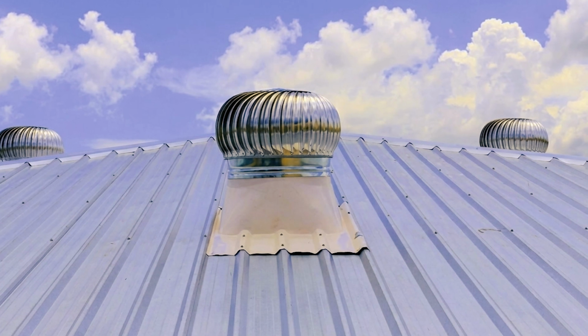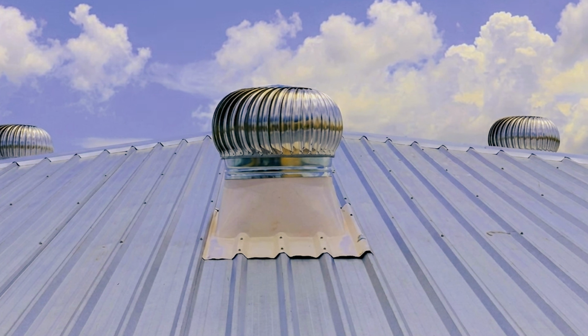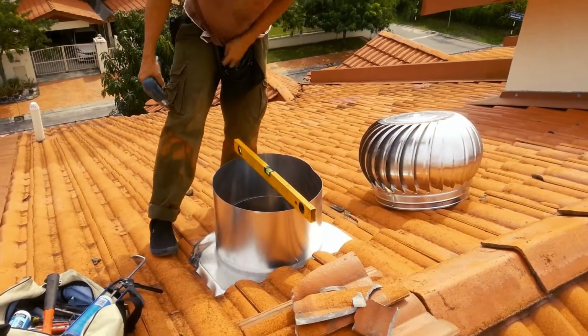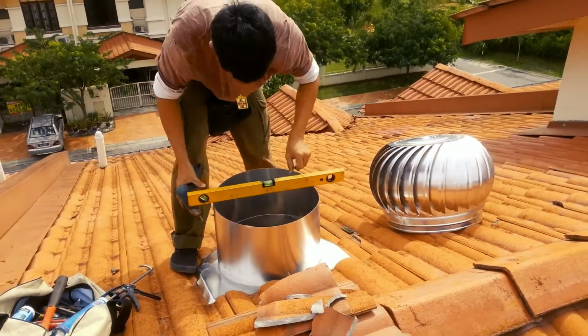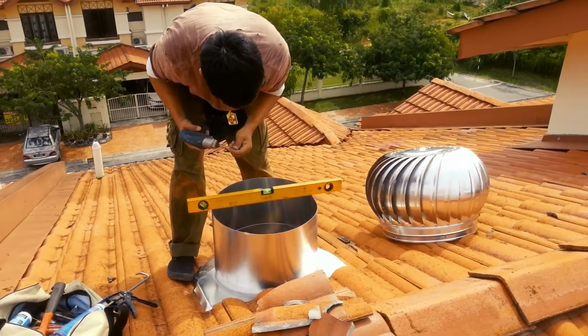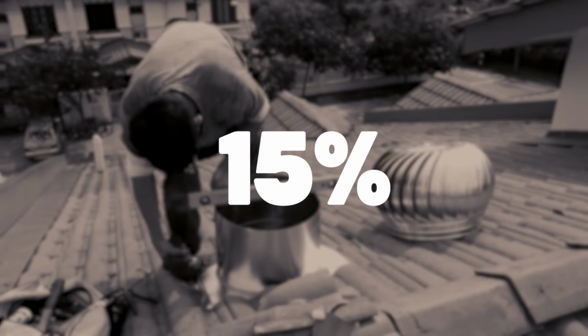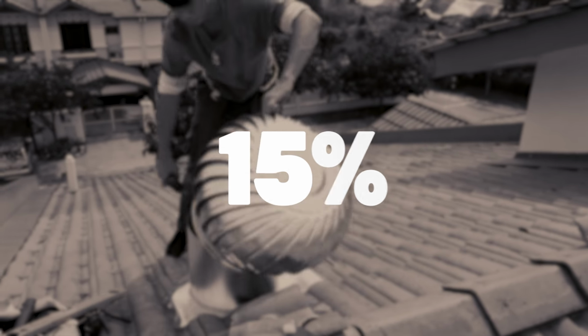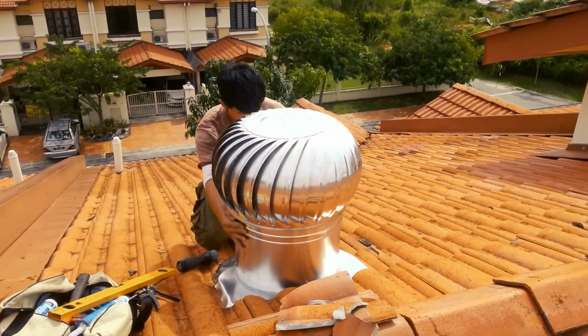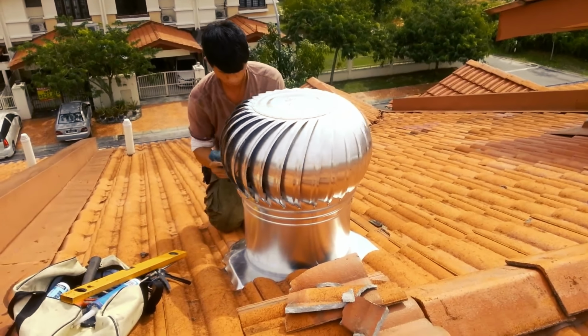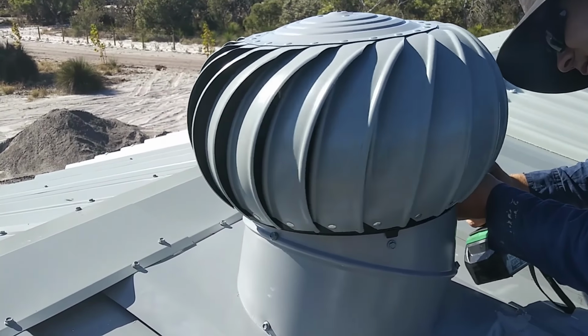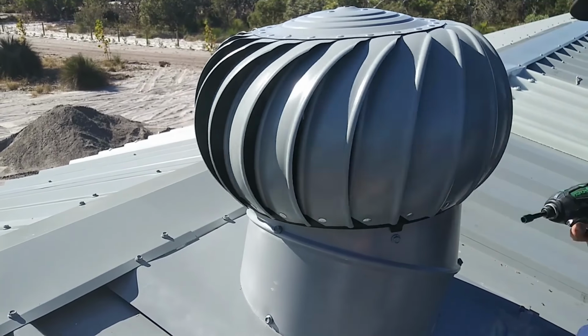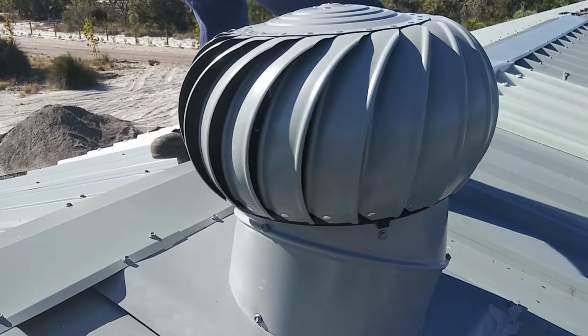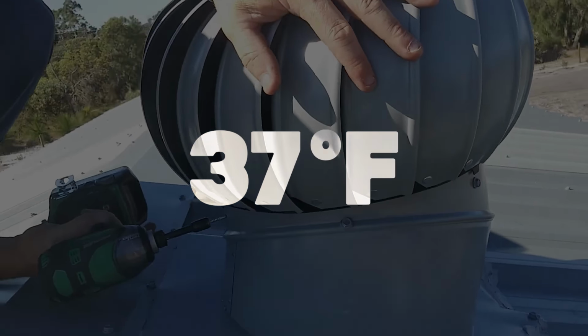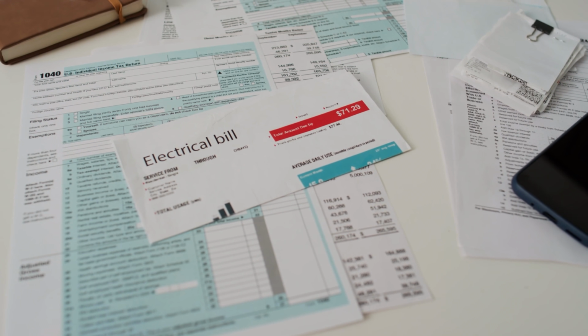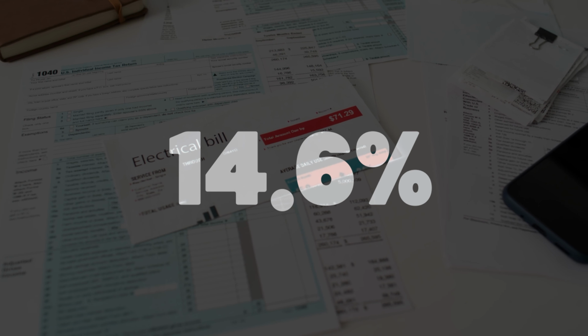And this simple design has been proven to be remarkably effective. A study by the Air Infiltration and Ventilation Center found that installing a turbine ventilator increased attic ventilation rates by an average of 15% over a full year, with improvements of up to 50% when the wind hit the unit from its optimal direction. And data collected in the San Diego area showed that a properly installed turbine system reduced peak attic temperatures by as much as 37 degrees Fahrenheit, which translated to an average energy bill reduction of 14.6%.